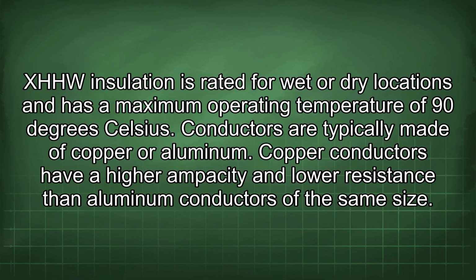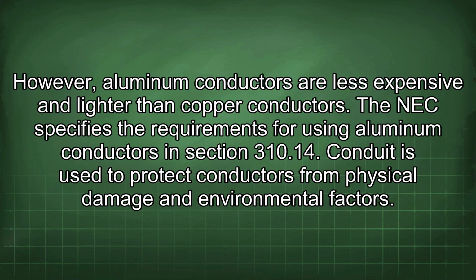Conductors are typically made of copper or aluminum. Copper conductors have a higher ampacity and lower resistance than aluminum conductors of the same size. However, aluminum conductors are less expensive and lighter than copper conductors. The NEC specifies the requirements for using aluminum conductors in section 310.14.